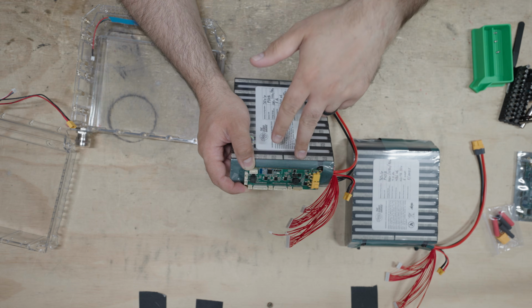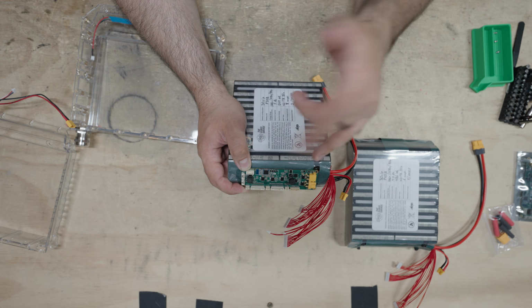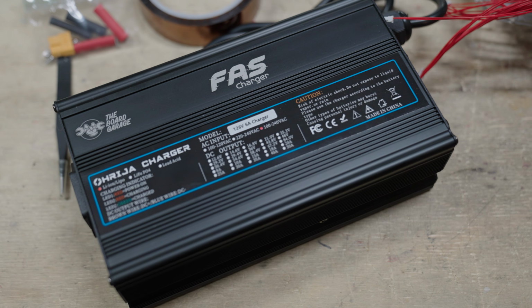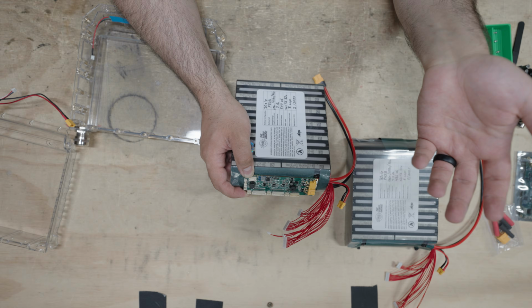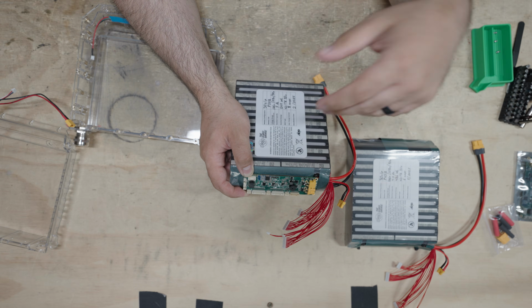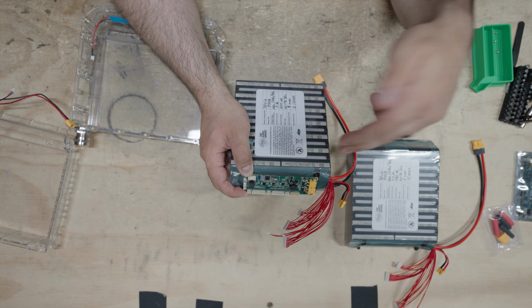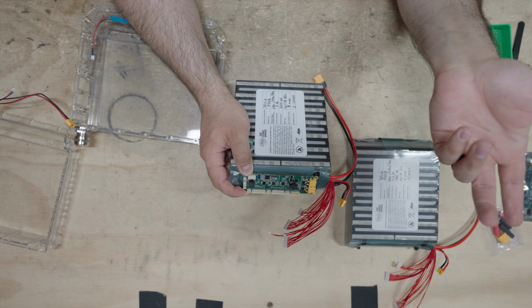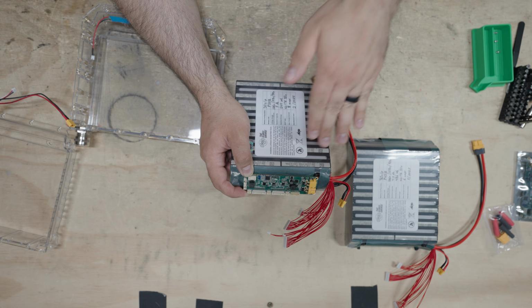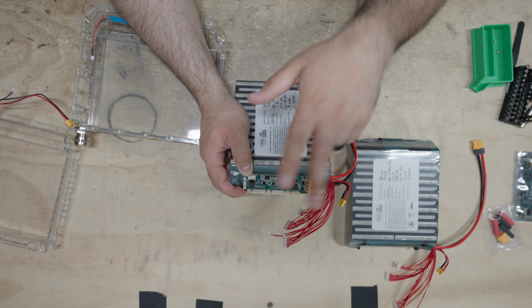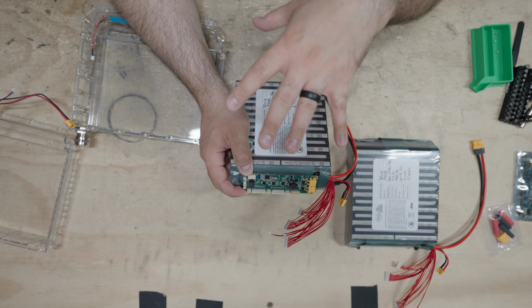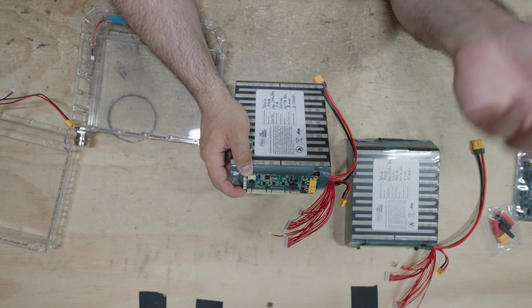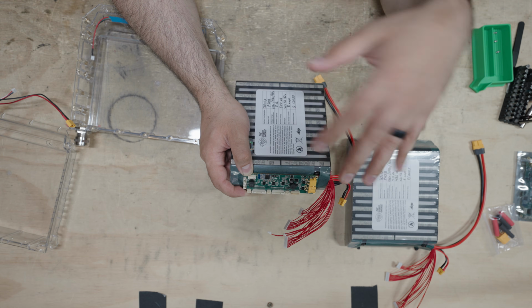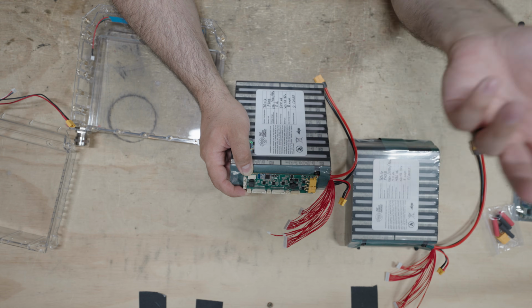In addition, there's an air gap below this, and while fast charging, which can get this battery from 0 to full in less than an hour (about 45 to 50 minutes depending on the cell being used), this will of course heat up at that higher charge current. With the air gap and isolation between this and any other sensitive material in the battery area, you'll have less effect of the BMS's heat on anything else that might be affected by it.